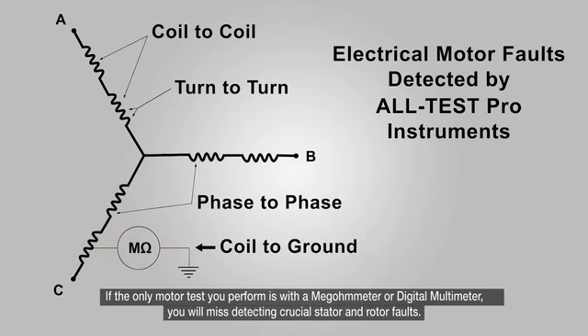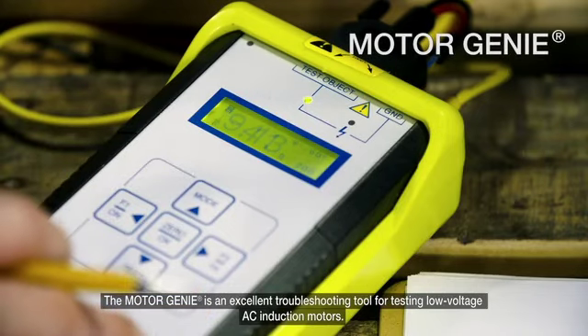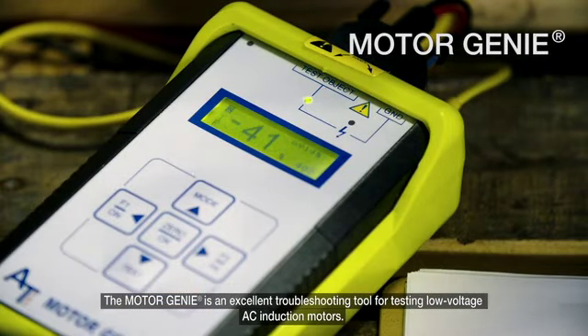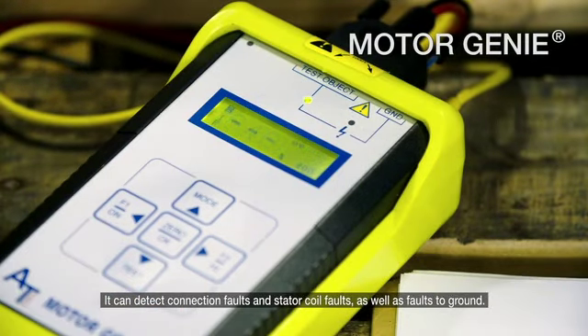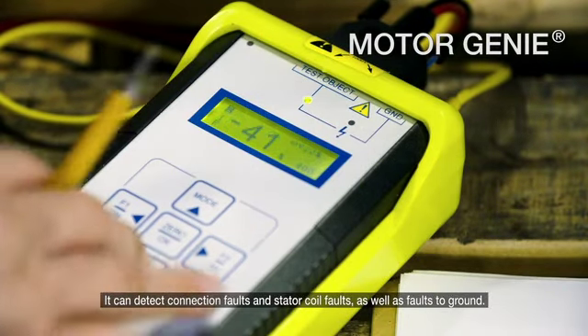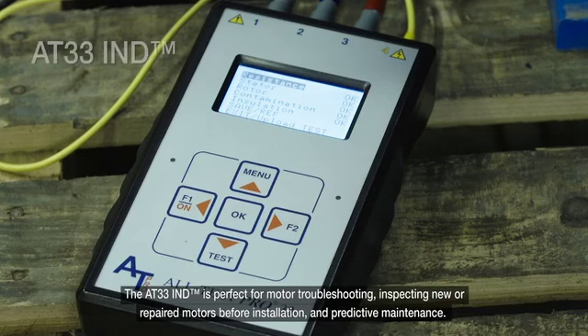and rotor faults. The Motor Genie is an excellent troubleshooting tool for testing low-voltage AC induction motors. It can detect connection faults and stator coil faults, as well as faults to ground. The AT33 is perfect for motor troubleshooting, inspecting new or repaired motors before installation, and predictive maintenance.